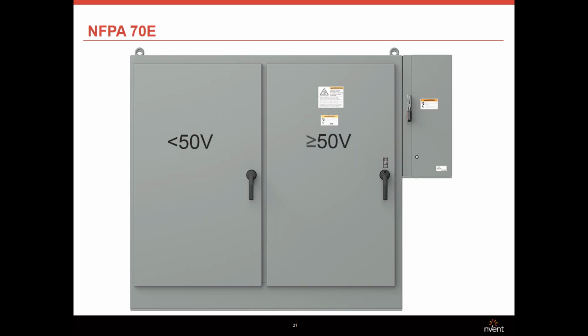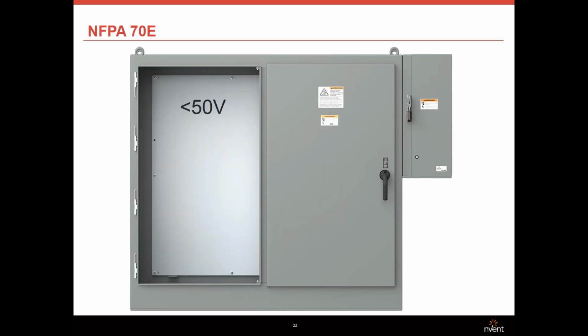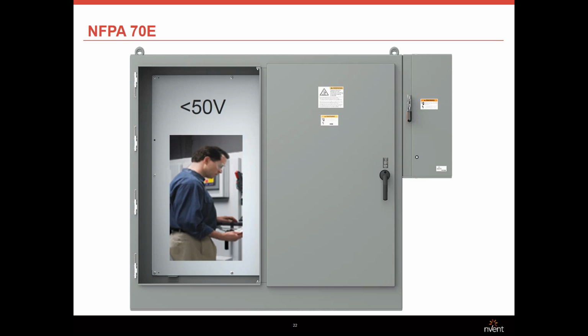energized electrical conductors and circuit parts that operate at less than 50 volts shall not be required to be de-energized where the capacity of the source and any overcurrent protection between the energy source and the worker are considered, and it is determined that there will be no increased exposure to electrical burns or to explosion due to electric arcs. What this means is that for an enclosure operating under 50 volts and under 1.2 calories per square centimeter, there is no level of PPE that is required.